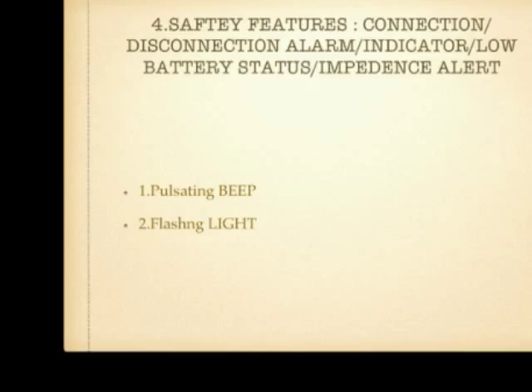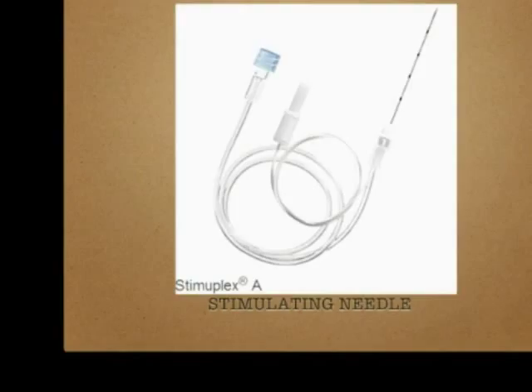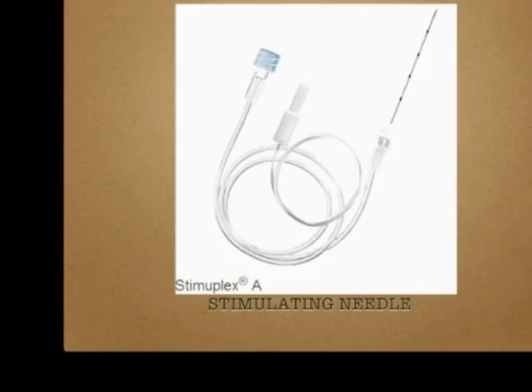There should be safety features such as a connection/disconnection alarm, low battery status alarm, and an impedance alarm, which may appear as a beep sound or flashing light. You should have the ability to choose the frequency from 1 Hz to 2 Hz. The stimulating needle shaft is fully coated and insulated except at the tip, where electrical pulses are discharged. Needles come in sizes of 2.5 cm, 5 cm, 10 cm, and 15 cm with centimeter markings. The extension tube should be clear and transparent so that blood can be detected early if the needle is over a blood vessel.